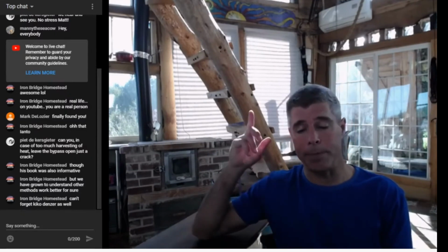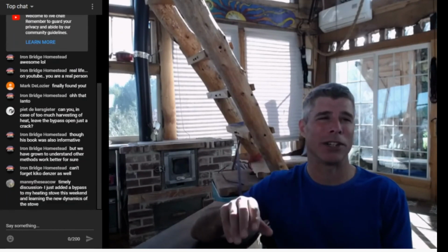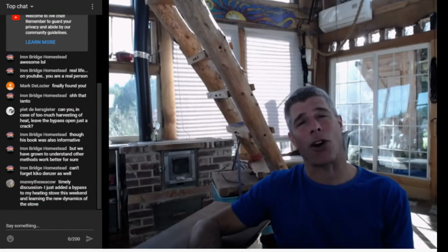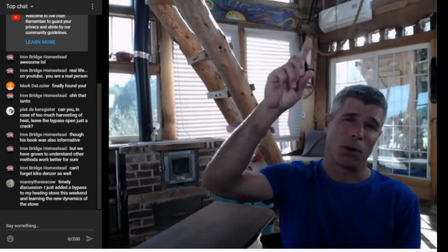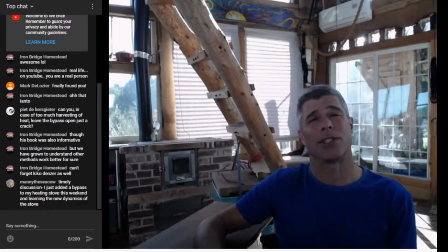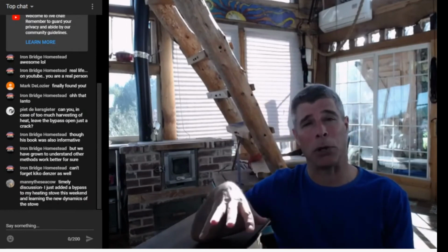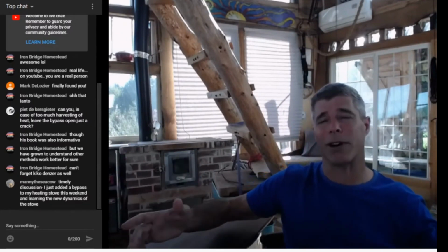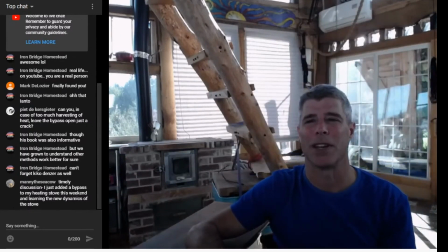And with that said, I will say when you're laying out your stove and trying to find where it's going to go, it's a really good idea to start from the chimney exit, because you're going to need to go in between rafters or beams up on the ceiling. And so it's a good idea to make that hole, use your plumb bob, drop it down there, center your stove's chimney exit on that plumb bob and build around that. That's usually the best way to go about locating your install in your space. You can get it close on the floor, look up, figure out where the chimney goes, plumb the chimney, and then you're good to go.